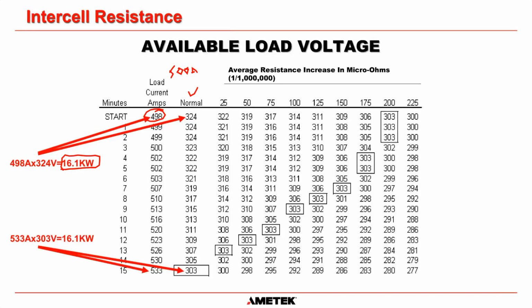For this test to be accurate, we have to maintain 16.1 kilowatts out of the battery at all times. At the very end, at the 15-minute mark, our voltage as the battery discharges has gone down to 303 volts. That means the current has to go up. If you multiply 533 by 303, you get 16.1 kilowatts.